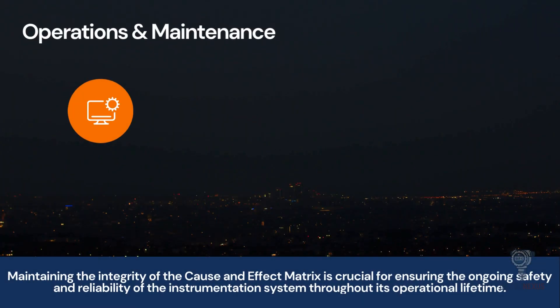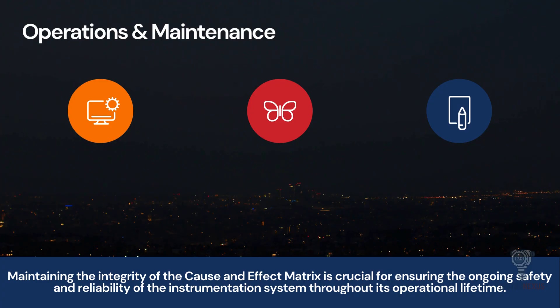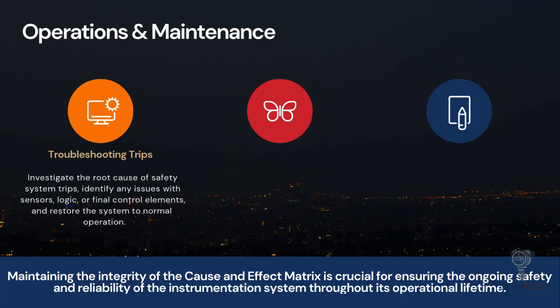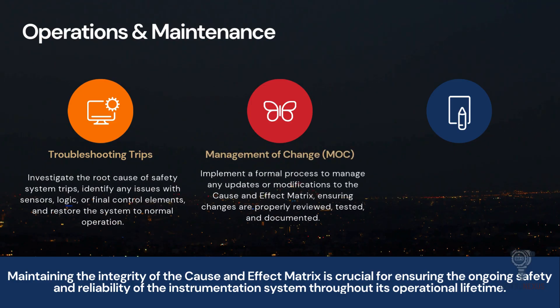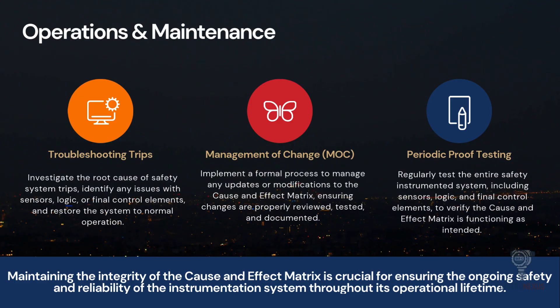After the plant is running, the cause and effect matrix enters the operations and maintenance phase. Operators use the matrix for troubleshooting trips — if the plant shuts down unexpectedly, they consult the matrix to trace the root cause and identify which sensor triggered the event. Crucially, we must implement management of change. If we need to change a trip setpoint, it must go through a formal review and documentation process. Finally, we perform periodic proof testing to regularly test the entire loop and ensure the system hasn't degraded over time and that the matrix is still functioning as intended.